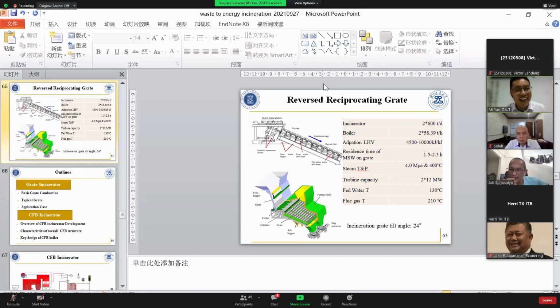Okay Professor, thank you for your question, it's a very professional one. Based on my experience and knowledge, we have to consider two or three points. First, for the MSW incinerator, the temperature cannot be as high as with coal, because of corrosion. Usually the steam parameter is 400 to 450 degrees, and the pressure can be higher, but we cannot increase the temperature further - it will worsen the corrosion. So we have to set a reasonable steam temperature, because the steam temperature influences the heat exchanger, and corrosion usually happens on the surface of the heat exchanger.